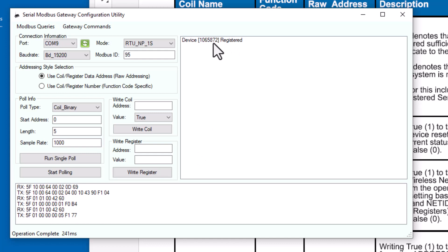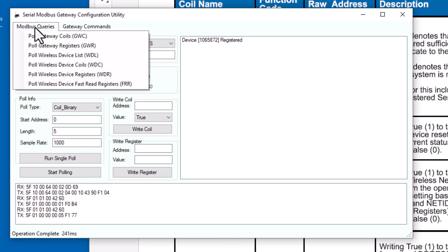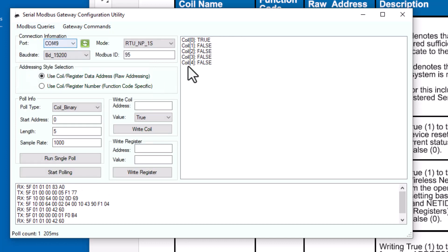The ID number on this one when I look at the code is 1065872. We're going to put it in the first slot, or slot zero, put a zero in there, click on OK. Perfect, it says now that the device is registered. So now I can come back over and just double-check because our status should have updated, which it did. If I look physically at the gateway device, that bottom LED has now gone from red to green showing that the wireless network is active.